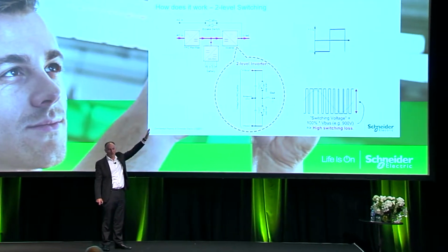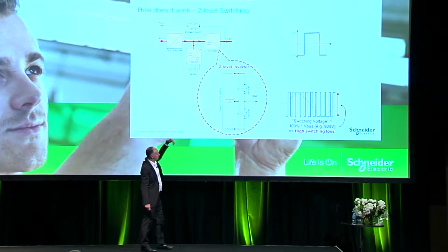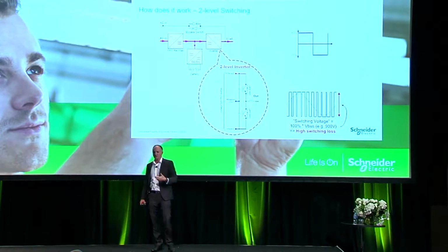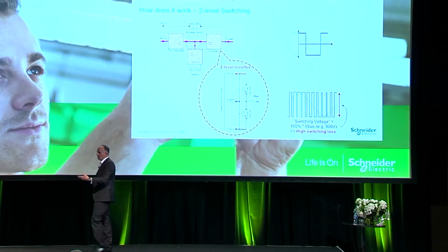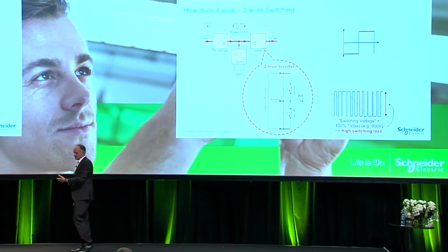So you've got two devices and you're switching your full 900 volts and you're stepping and producing a waveform, which is then pulse width modulated and goes through a filter to produce a nice output sine wave. And that's the way pulse width modulation works and produces a sine wave. Challenge with this is you've got 1200 volt devices sitting in there, you've got 900 volts and they're working pretty hard. So it's a bit like my maximum heart rate is 170 or 180 or whatever it is for my age, but I'm constantly running at 3/4 of that. So I'm wearing out a little bit. So we want to try and get the heart rate of the system down.